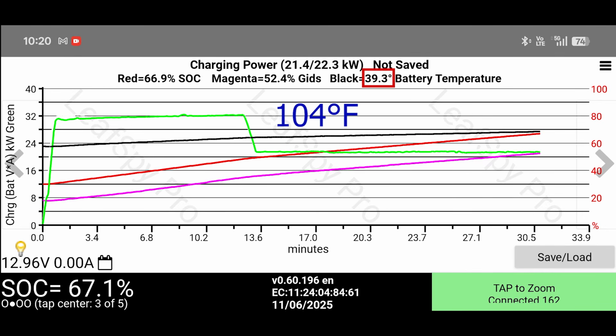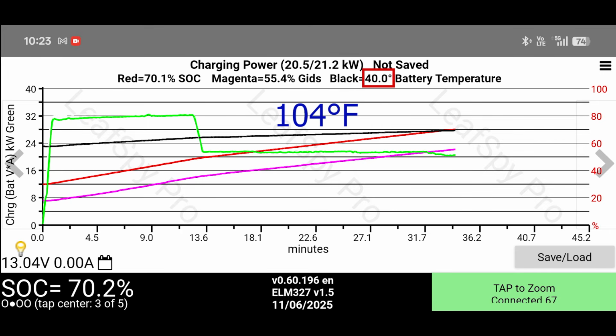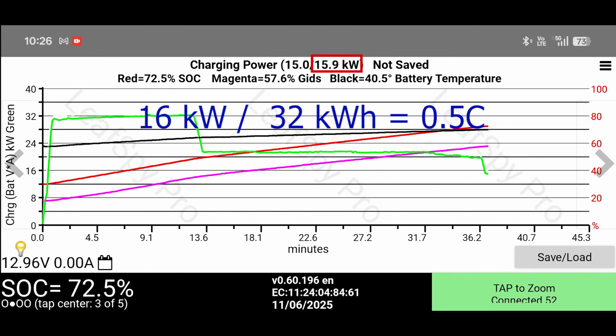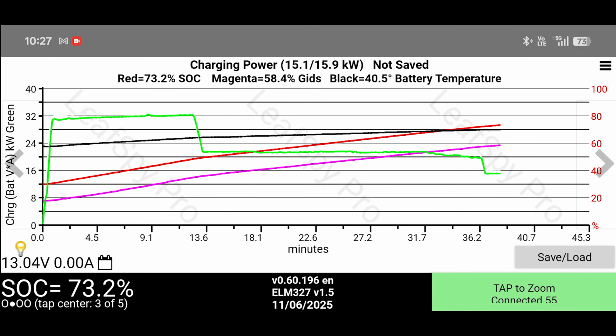When the temperature was 40 plus, the charge power dropped down to around 16 kilowatts, which is a 0.5 C charge rate, which is actually ideal for NMC chemistry to sustain continuously. In a perfect world, the battery should be between 25 to 35 Celsius when being charged at a 0.5 C rate. But I'd say this is a nice improvement compared to what we get with the stock Nissan BMS programming.